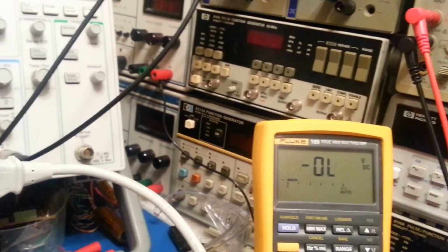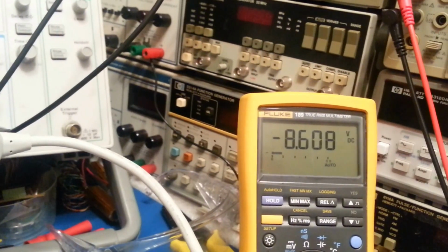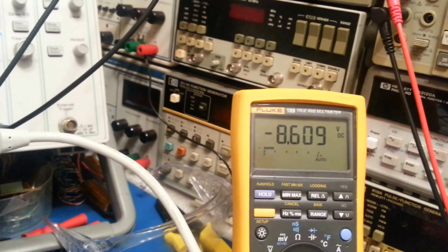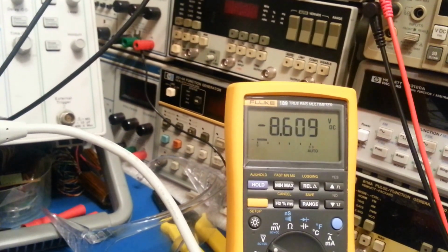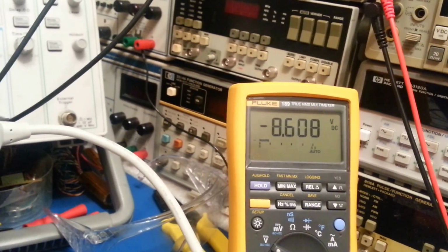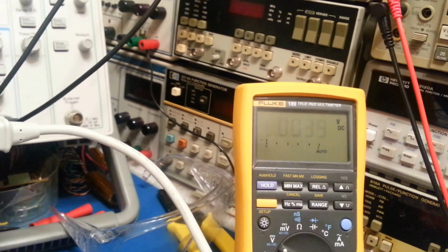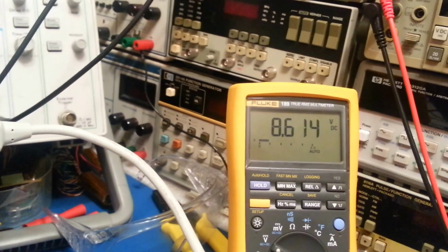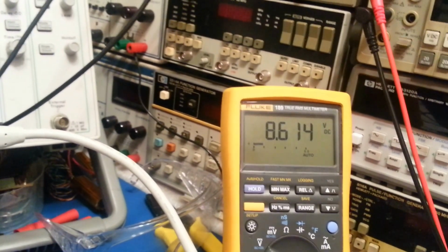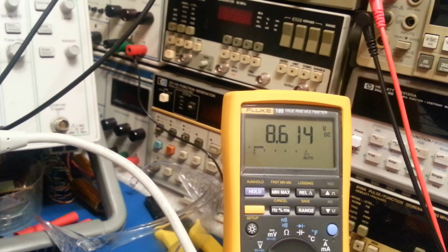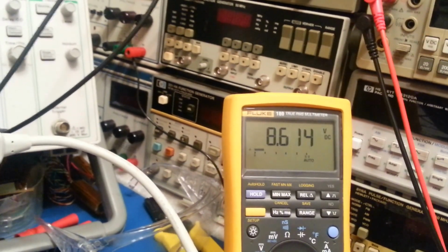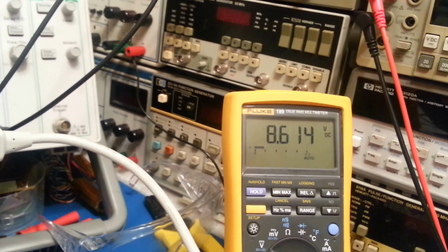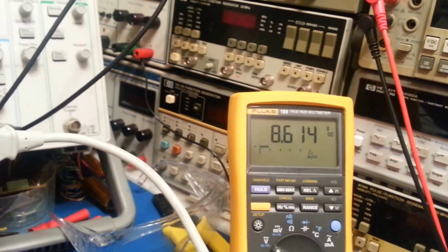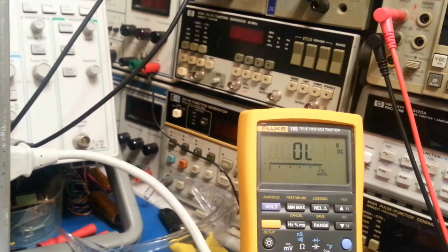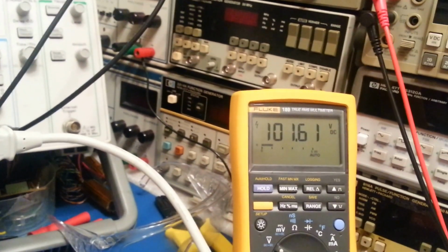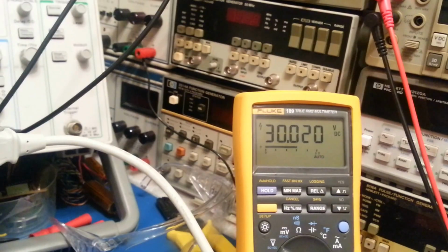I think the minus 8.6 is the one that is very tight. The tolerance is only about 10 millivolts above and below 8.6, and this one is within, so it's perfect. And the positive 8.6 as well. Both the positive 8.6 and the minus 8.6 are used to bias all the analog circuitry, so their tolerance is quite tight, and as you can see, the scope is perfect. I haven't touched it; it just arrived like that. The 100 volt is also bang on, and then there's the 30 volts. They were all perfect.